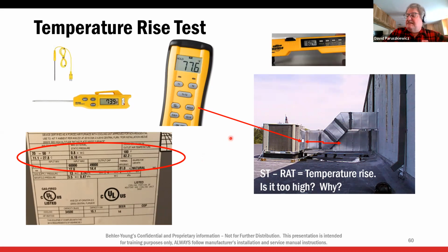Now, I have had guys say, well, at test, I got a 40 to 80 degree allowable temperature rise, and I have a 70-degree rise. Well, the other thing we got to look at is return air temperature. How high is it? Okay. Now, a lot of duct systems, what we do is we use a plenum return. So we got a 20-foot high building, right? And the ceiling's at 8 feet, 10 feet. You got 10, 12 feet above it. And you're using the whole plenum as a return. So you got a little drop out of the bottom of the curb for your return.